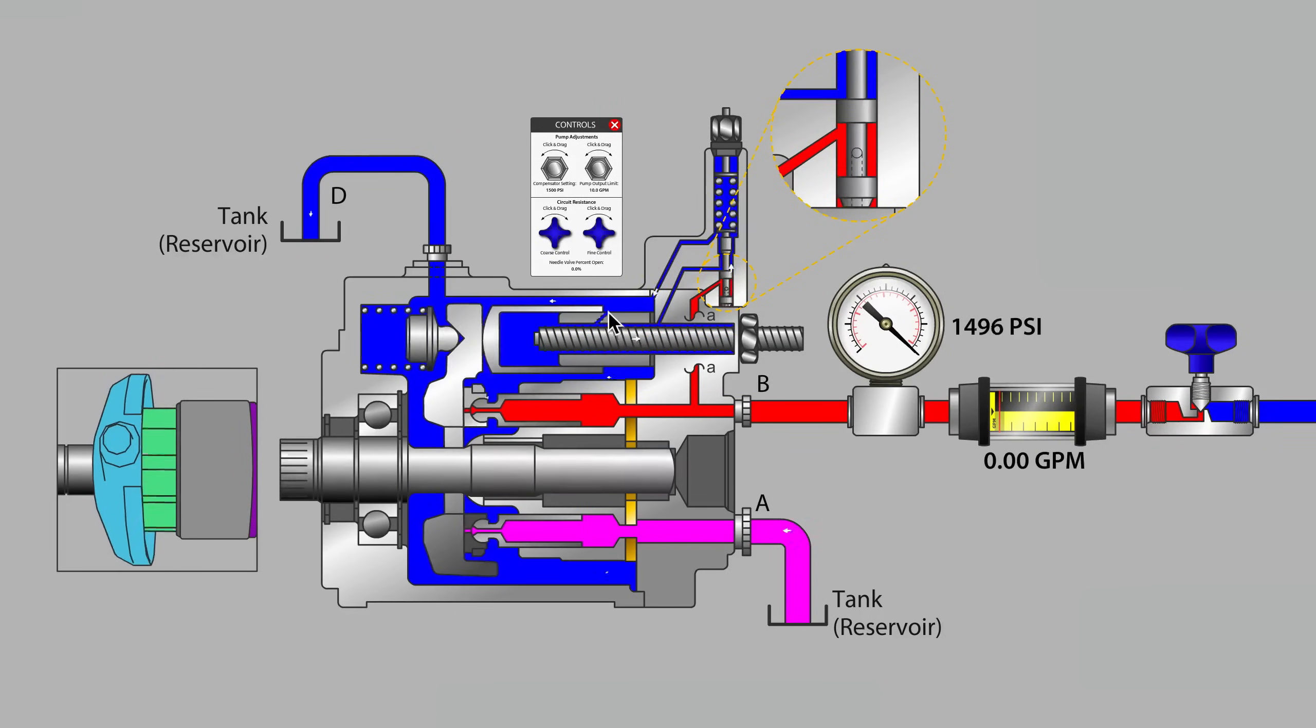To limit the travel of the swash plate once we reach the zero point, quite often a bleed orifice is present on a tube where the control piston is sliding back and forth. So that's another clearance inside the pump where case drain flow originates from.